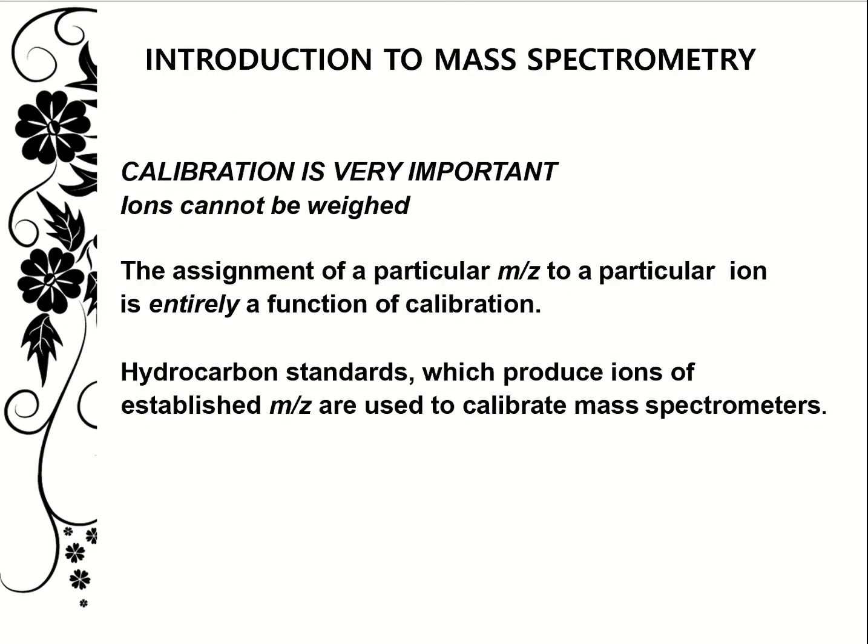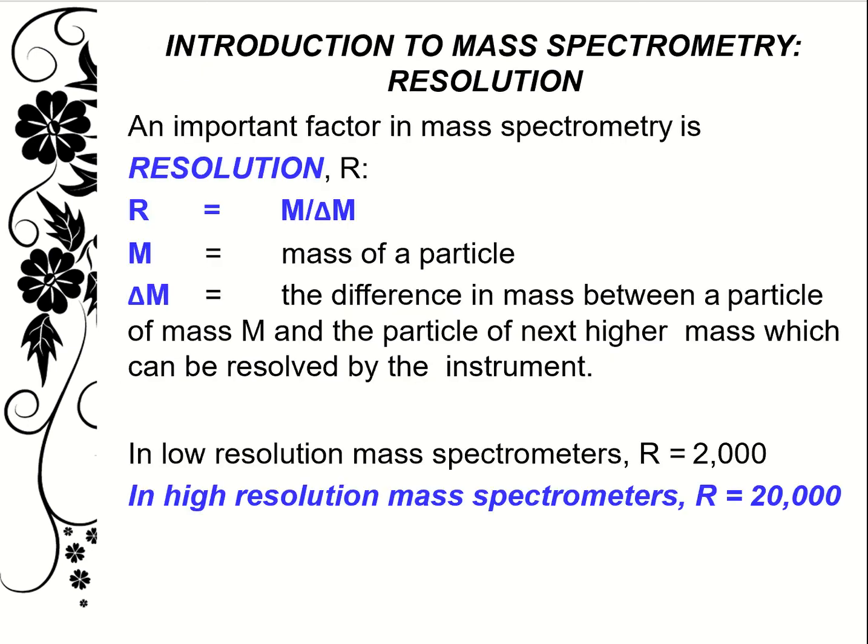Calibration is very important in mass spectrometry. Ions cannot be weighed, so the assignment of a particular mass-to-charge ratio to a particular ion is entirely a function of calibration. Hydrocarbon standards, which produce ions of established mass-to-charge, are used to calibrate mass spectrometers.